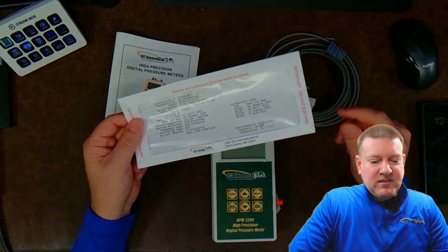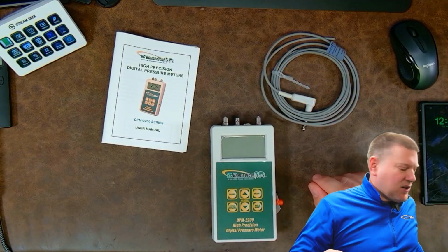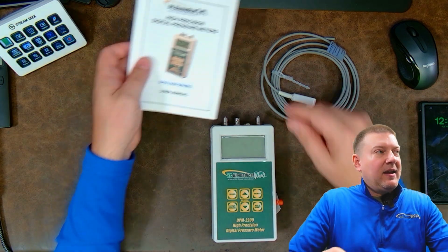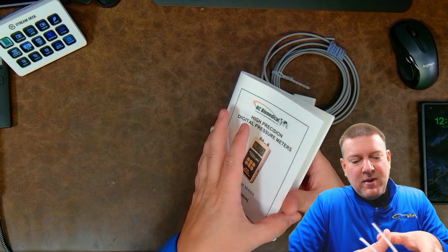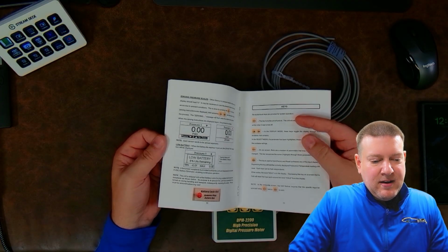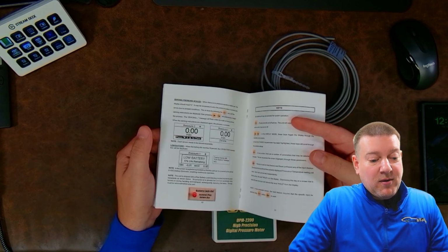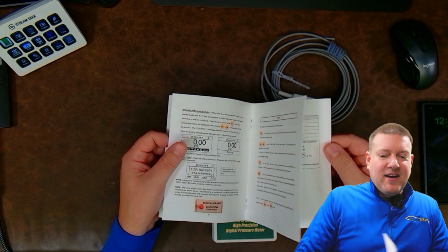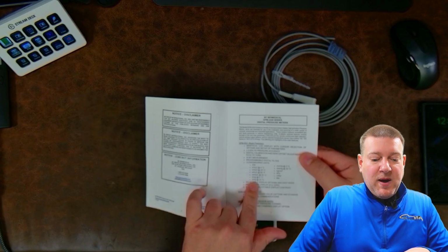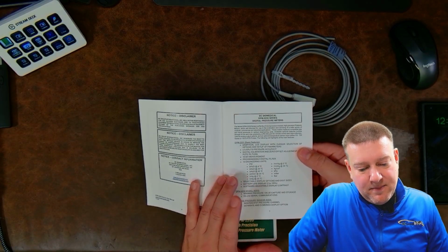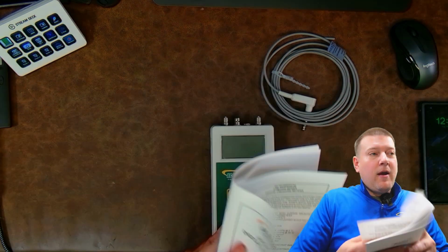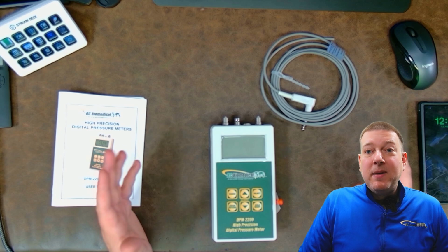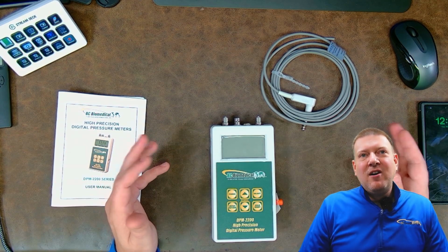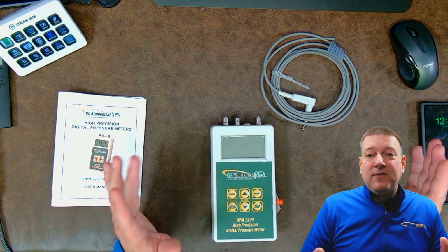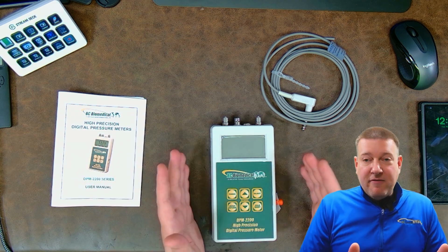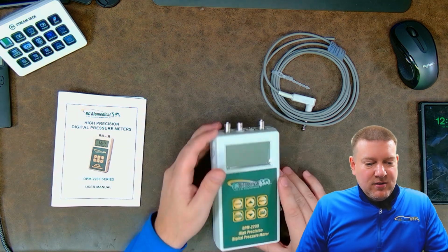Calibration certs. All BC items come with calibration certs. They are NIST traceable to the highest spec possible, and it has a user manual. User manuals normally are not as specific, and in some other manufacturers' cases, almost non-existent. But this one actually goes into a lot of detail, and it tells you a lot. However, if you're looking for the specs, it handles a wide variety of different engineering units. And since this is the Cadillac, it also has min and max, which I think is extremely important for pressure because it's too often that pressure fluctuates, especially if you're dealing with something that's got a leak. So if you have a min and max, you capture that automatically, no intervention required.